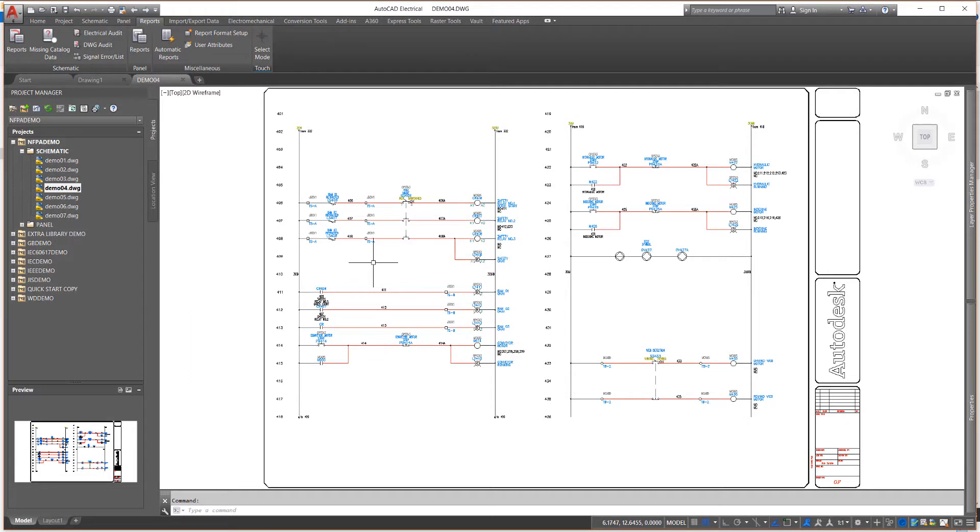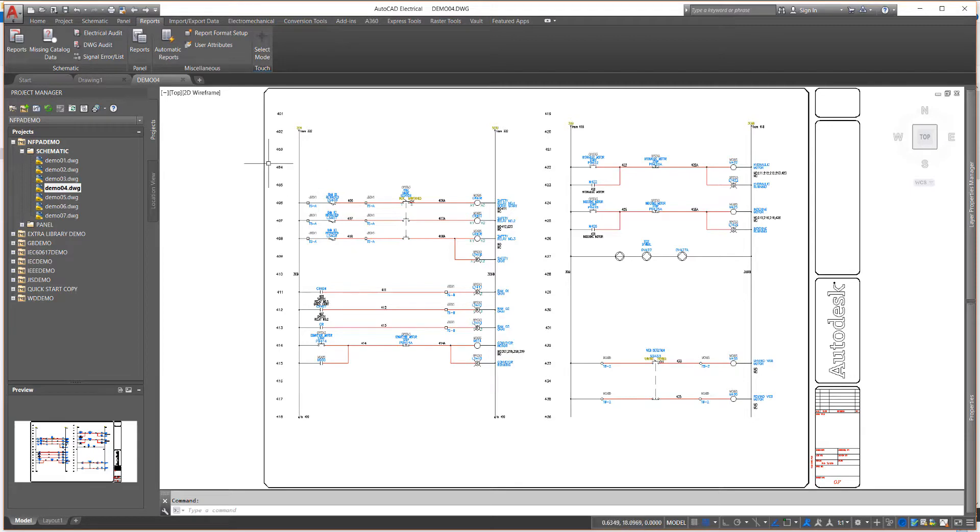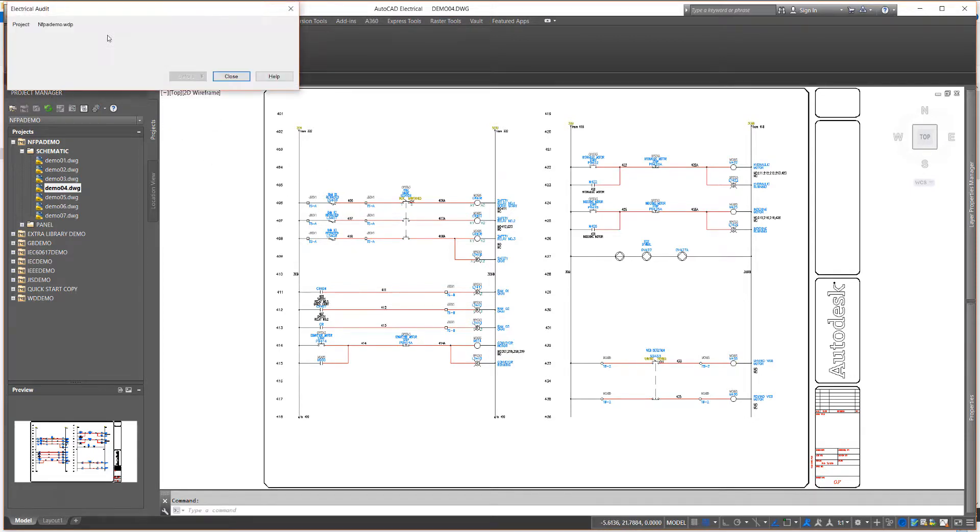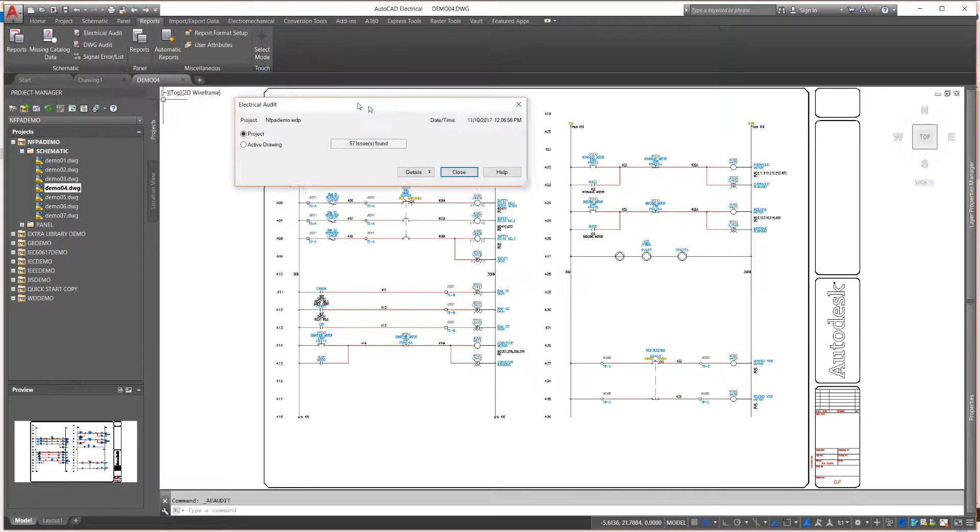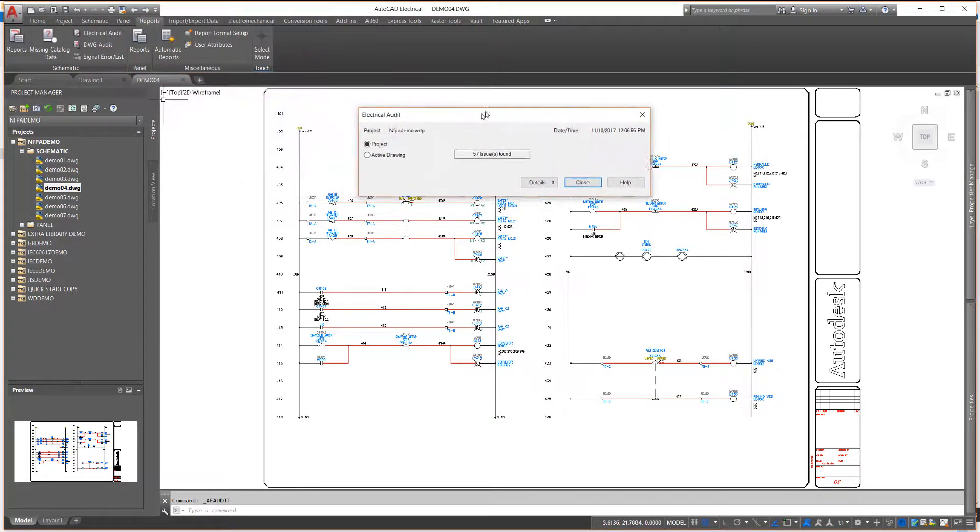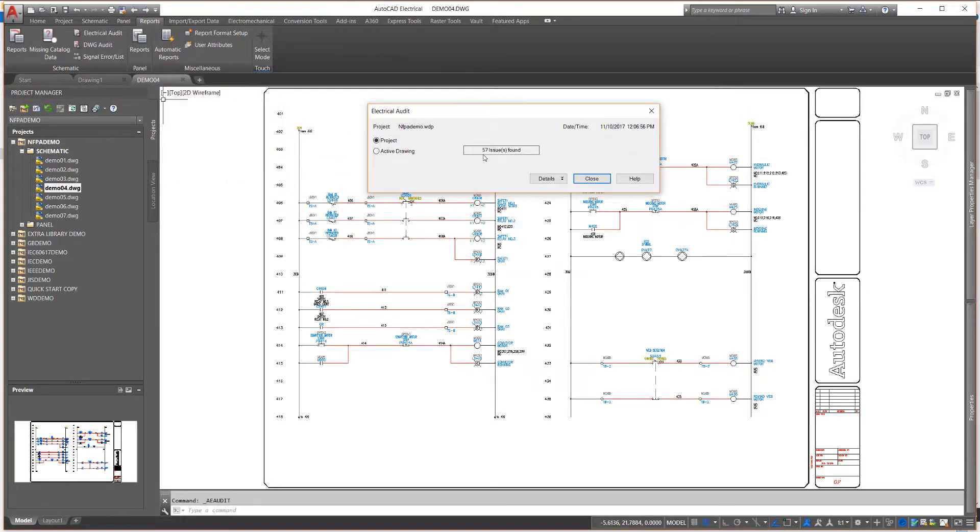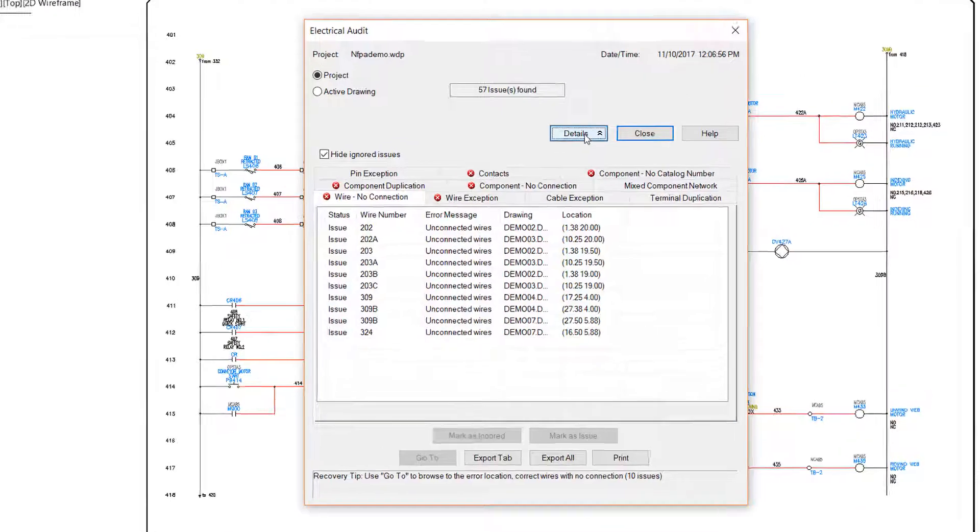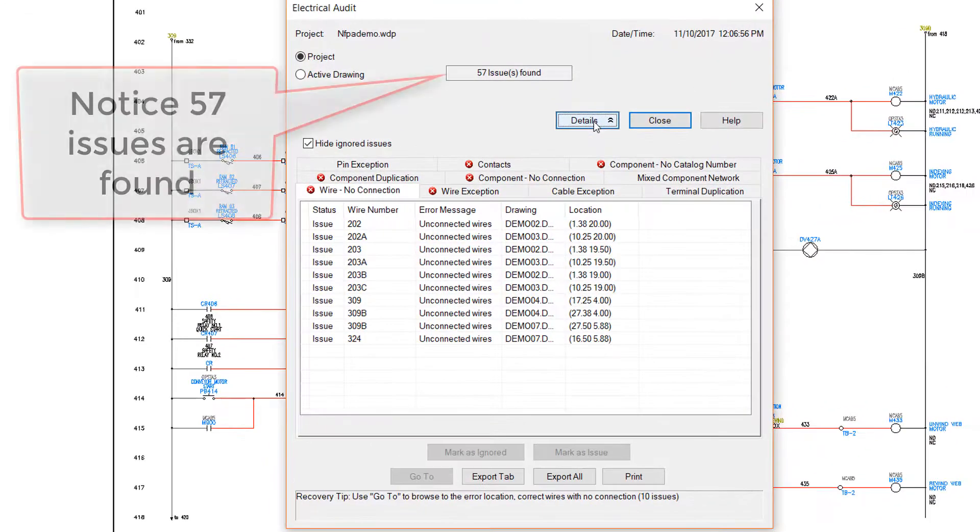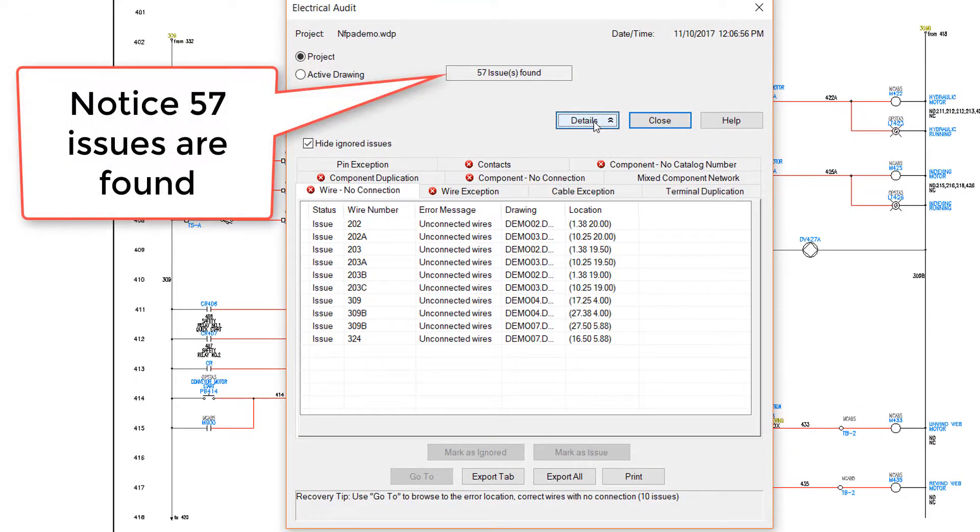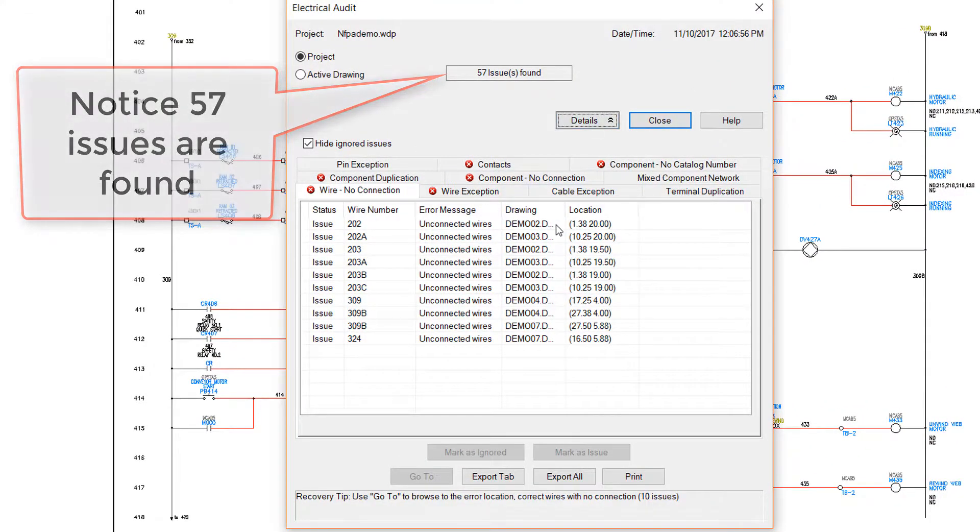At various points in a project, you may need to check the accuracy of your design work. Another of my favorite tools is the Electrical Audit Report, also found on the Reports tab schematic panel. The Electrical Audit scans the entire project looking for issues or discrepancies in 10 different areas. Any of the categories with the red X are where issues are found.